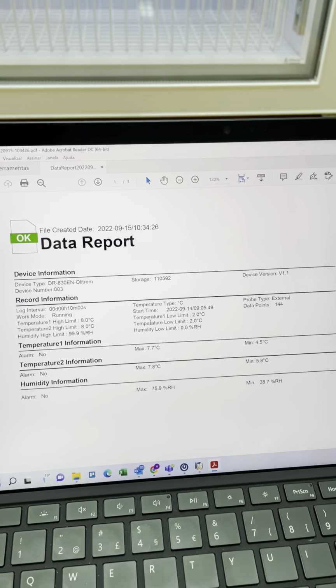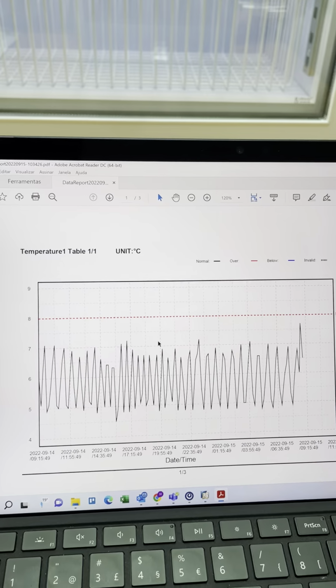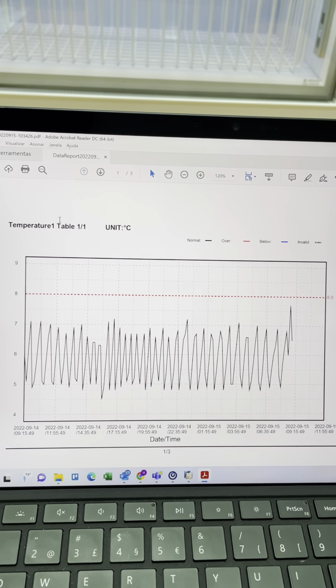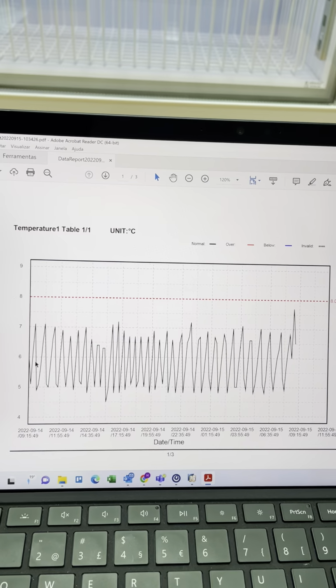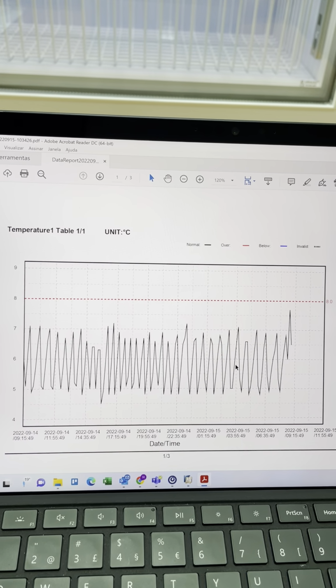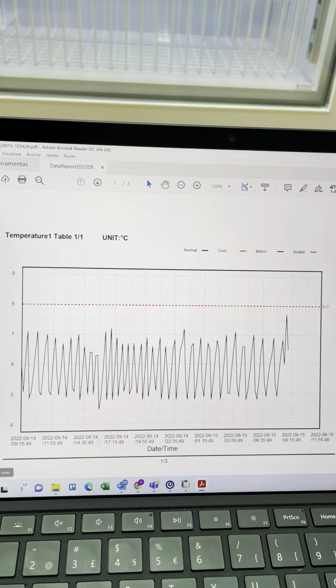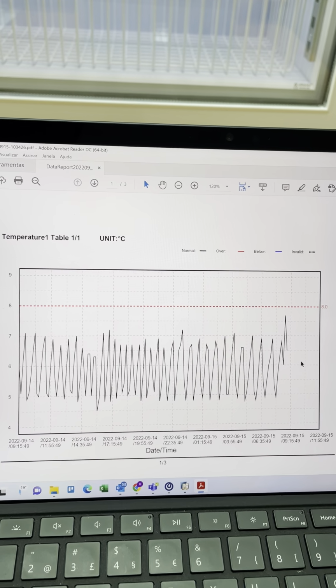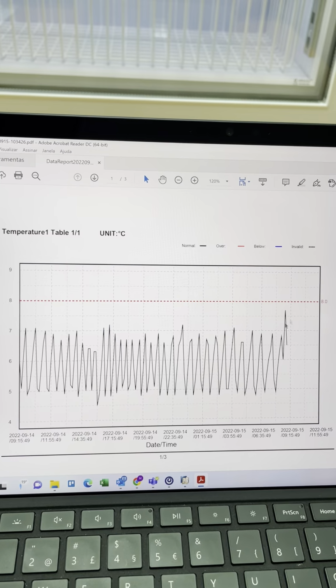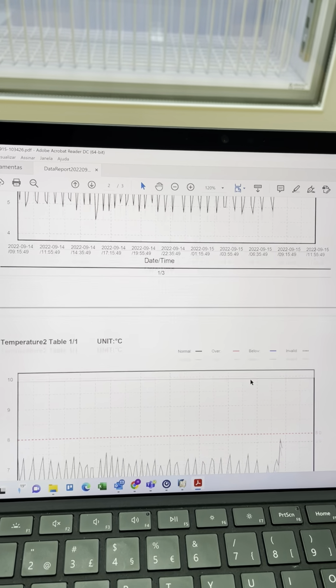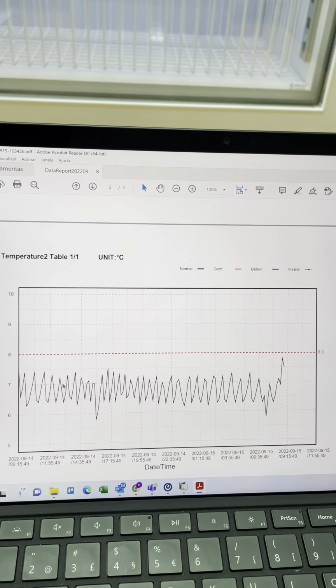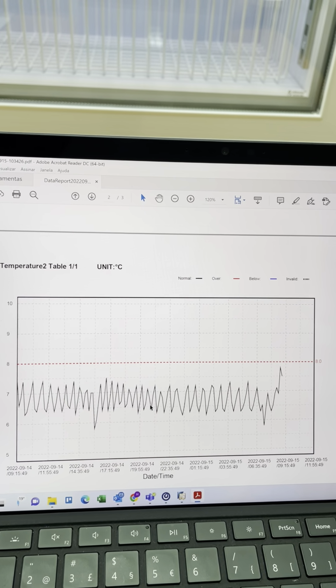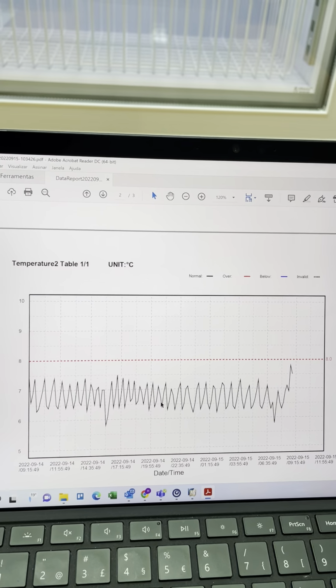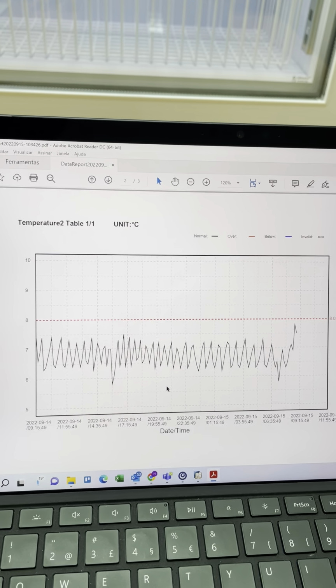In this case, we have an OK report. This is from other tests that we made first, and you can see many more points. So you can see here temperature 1, the air probe. You can see how the temperatures were during the time. You have the day and time here, and you can see how the temperature went inside the equipment. It didn't go above 8, so you don't have any alarm. Also, you have temperature 2. You can see that it's much more stable than temperature 1, because of course you don't have the effect of the open doors on temperature 2, the product probe.